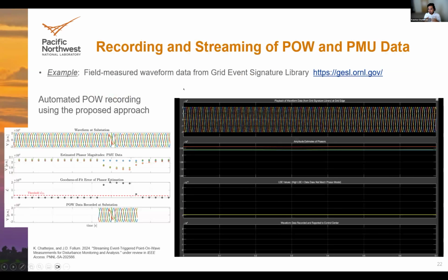Here is an example. Again, we picked a real field-measured waveform data from the grid event signature library. This shows that whenever your data is in ambient conditions, sinusoidal, you do phasor estimation and also the goodness of fit calculation. Your goodness of fit calculation is below the threshold, so none of your point on wave data is being recorded and reported.